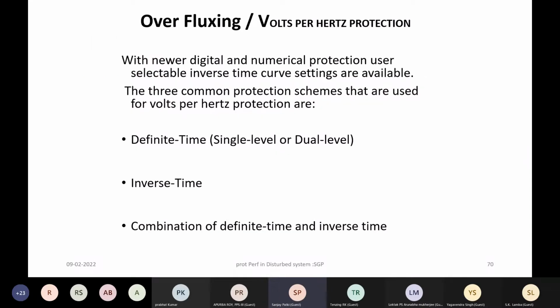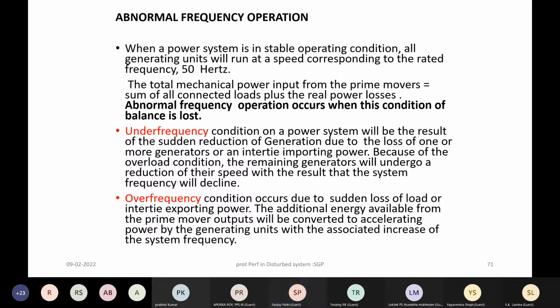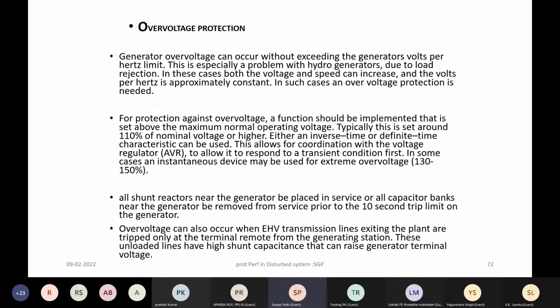So this overfluxing protection basically is a V by F, and this higher voltage accompanied by lower frequency can cause tripping of the transformers, especially interconnection transformers and generator transformer. Both are susceptible for tripping on overfluxing, and in many disturbances we have experienced that overfluxing protection operates in an undesirable manner.